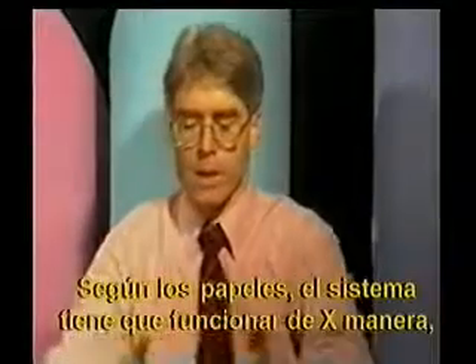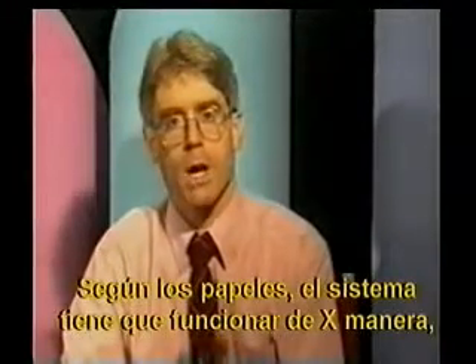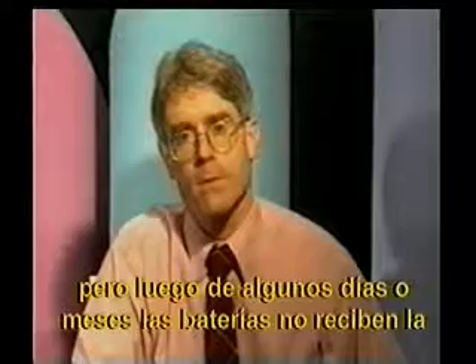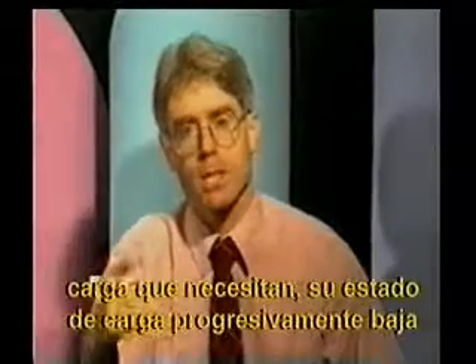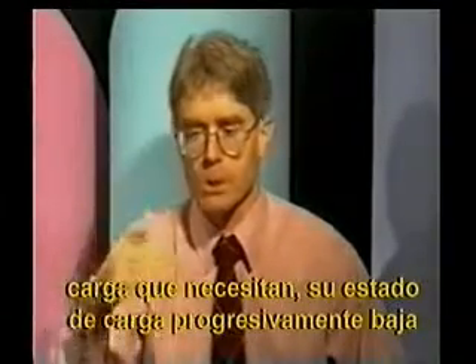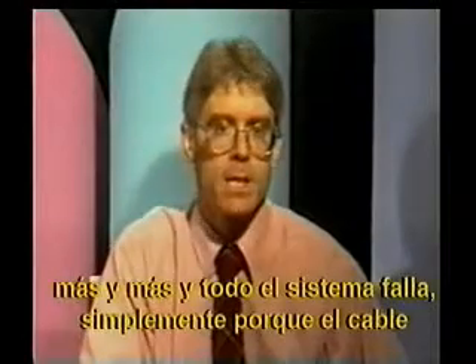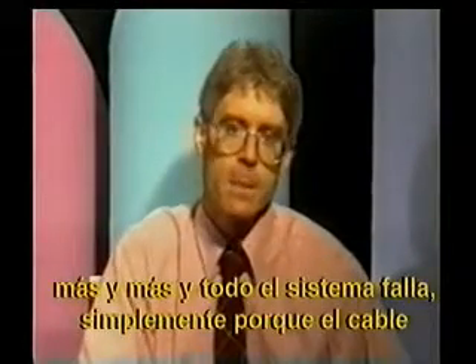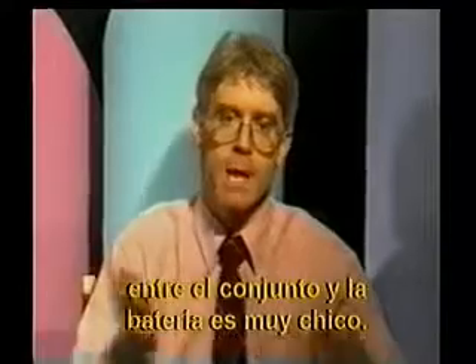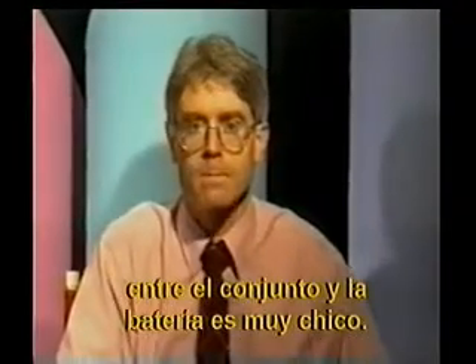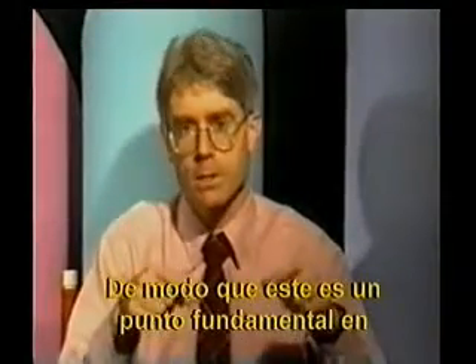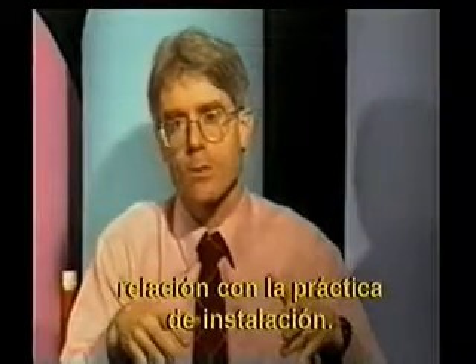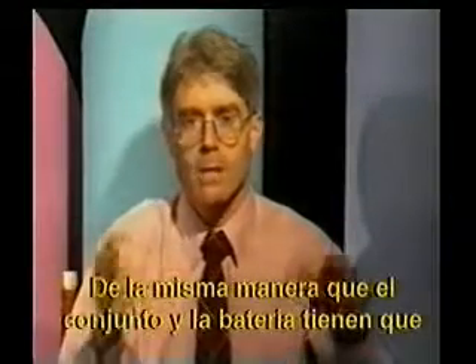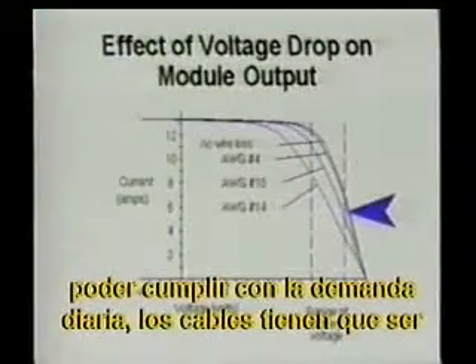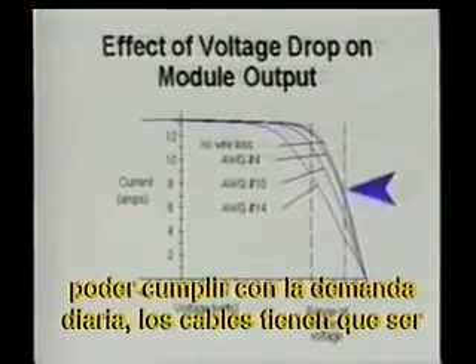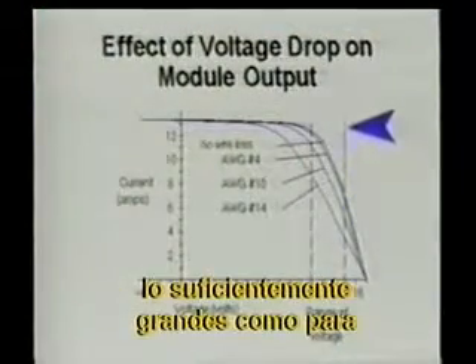So you can look at your paper and say the system should perform in such a way, but after a few weeks or a few months, the batteries would not have received the charge that they need. They'll progressively go lower and lower in state of charge, and eventually your whole system could fail, simply because the wire between the array and the battery was too small. So this is a primary focus in terms of the installation practice that we go through: size up your array and battery to meet your daily loads, and then size your wires large enough so that you have very little voltage drop, if any at all.